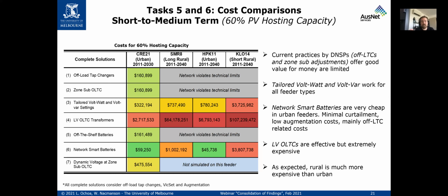For urban networks, it was found that really the only cost was changing the off-load tap positions, with a tiny bit of curtailment, almost none. By limiting the levels of reverse power flow, you need to augment less, and you can also manage voltages. But for rural feeders, the network smart batteries weren't as effective at managing asset congestion, so some augmentation was still required. This led to tailored settings actually being cheaper for rural networks, whereas network smart batteries were cheaper for urban networks.